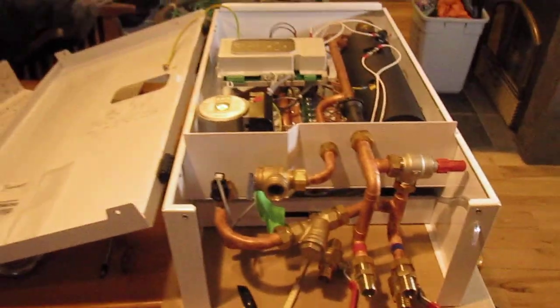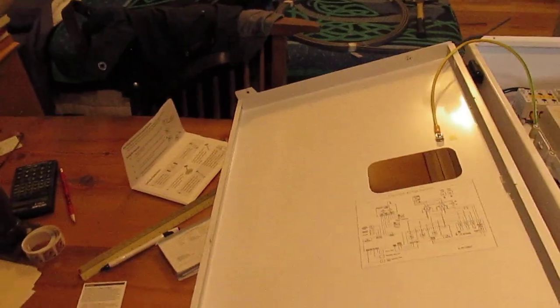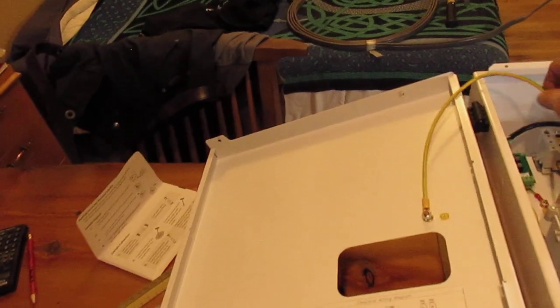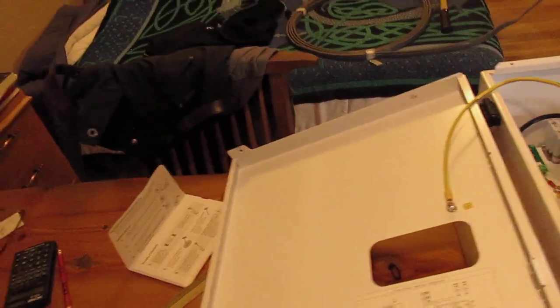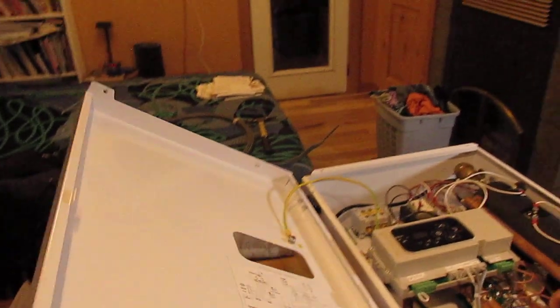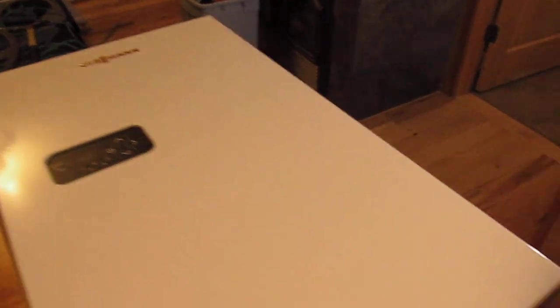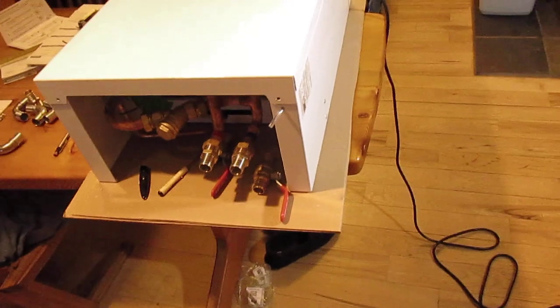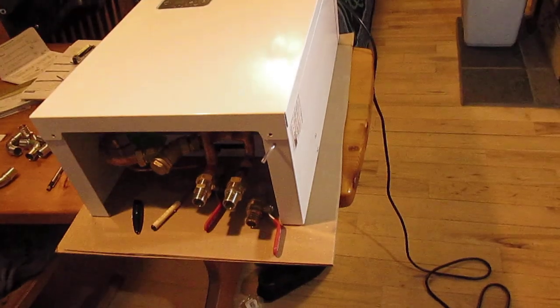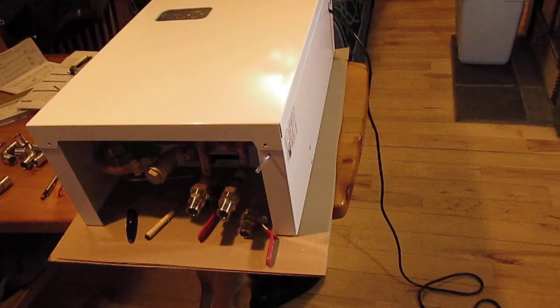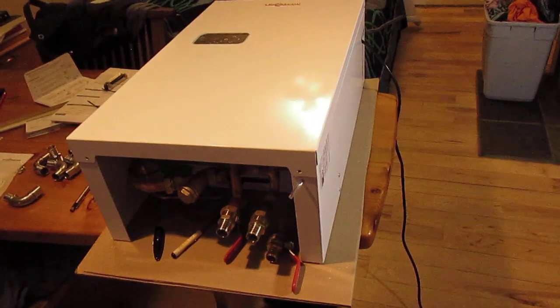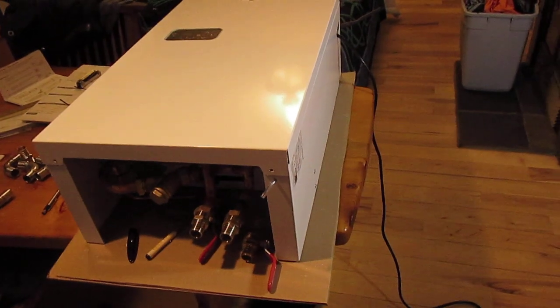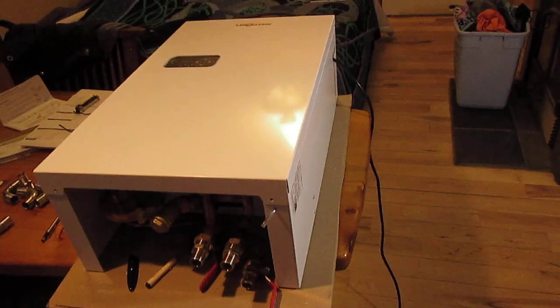But yeah, it's a really good boiler. I mean, I've had nobody call me, any complaints or anything. Once you get them up and running, they work really good. The challenging part is just getting there, doing all your build and stuff. And then I'm going to have probably a little bit of glycol in this. I don't think you should probably ever exceed 50% glycol. If you can get away without glycol, you're better off. It's too slippery and it likes to leak.